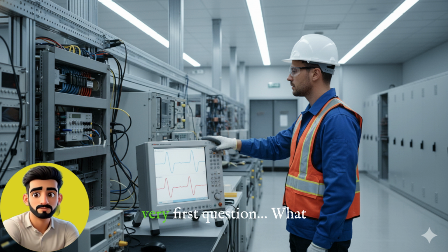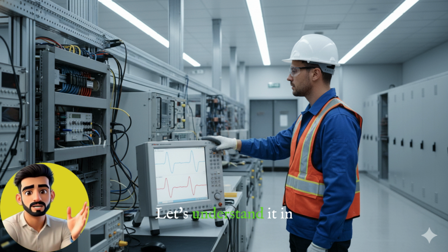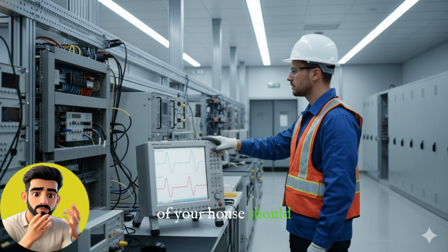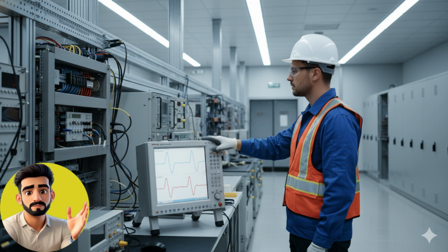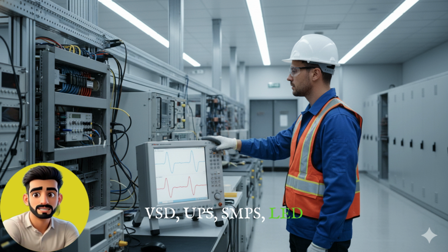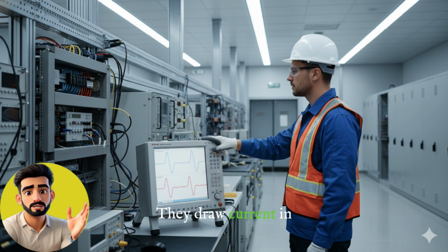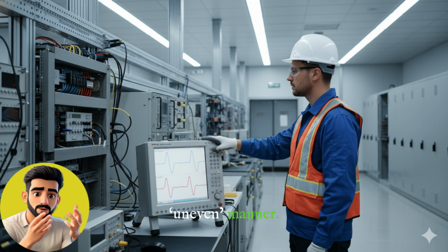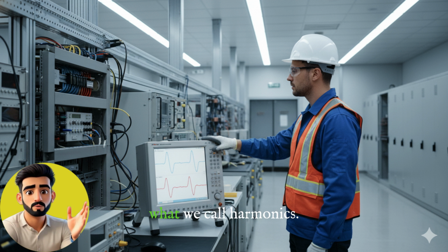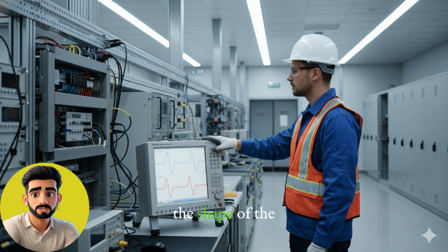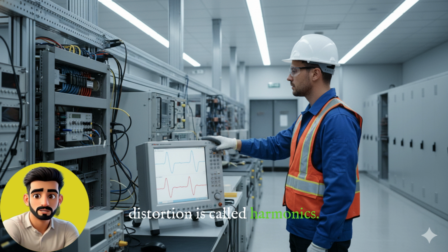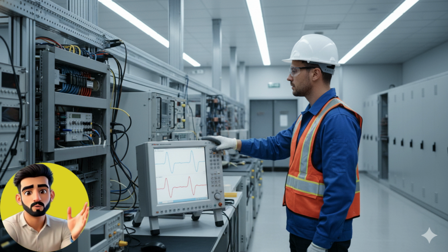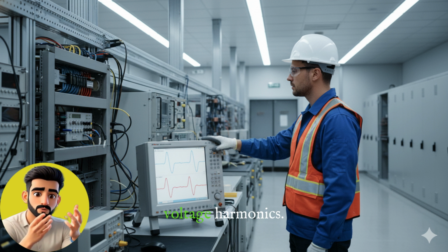Let's go, friends. The very first question: what is harmonics? Let's understand it in the simplest language. Imagine that the voltage of your house should be a perfect sine wave, smooth, clean, and completely round. But when some devices in the system, like VSD, UPS, SMPS, LED drivers, become non-linear loads, they do not draw current in a clean sine wave. They draw current in a cut, broken, or uneven manner. Result? The voltage also starts to convert into a broken shape. This distorted wave is what we call harmonics. In simple language, when the shape of the current gets spoiled, that distortion is called harmonics. And when many such distorted currents combine and also distort the system's voltage, that is called voltage harmonics.